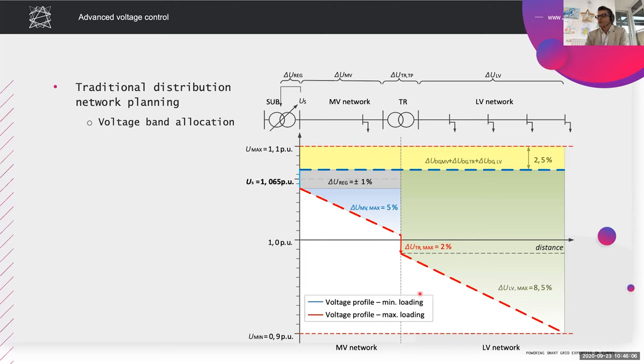What do you do if you exceed, I don't know, the 5% at medium voltage level? Well, you simply say, okay, the loading is increasing, the voltage drop is getting too high, we have to reinforce the network. The same on the low voltage level. If this voltage drop goes above the 8.5%, of course, this is only one case, you do the same, you reinforce the network. And of course, you take into account the worst operating conditions.